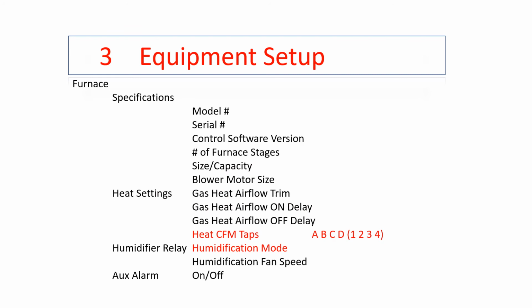Under the furnace setting, we have our heat settings here for the gas and heat airflow trim, the gas heat on delay and off delay. We'll also see our heat CFM taps here, A, B, C, D, or 1, 2, 3, 4, depending on your schedule in your book. It does default on 2. At any point your customer feels it is too hot or too cold, you can go in and do trim rates using your trim, or you can set your heat CFM taps. This normally would have been done on the dip switches, and now it's done at the Daikin 1 thermostat.